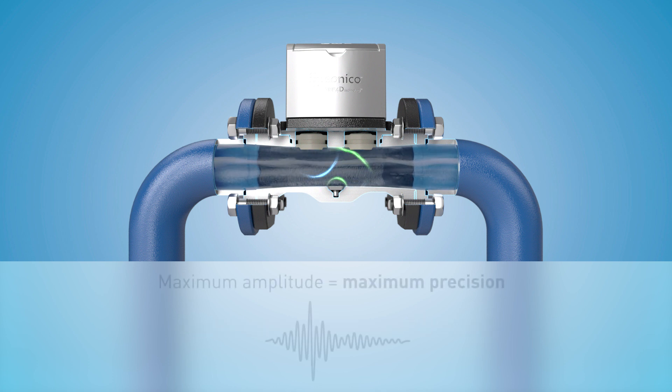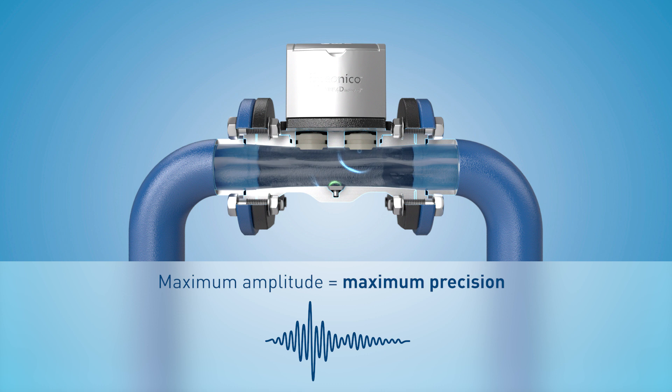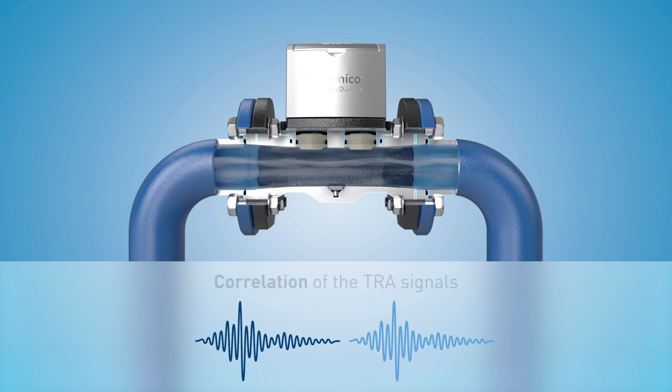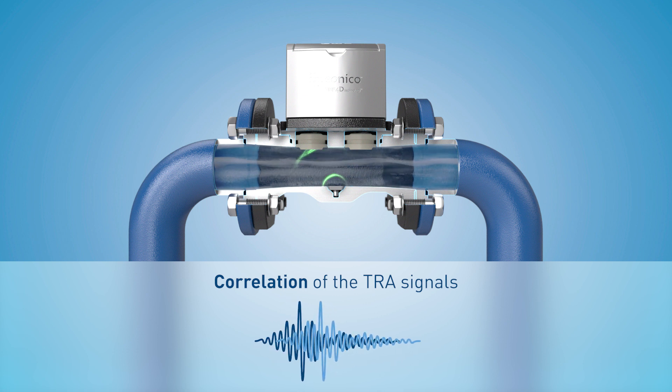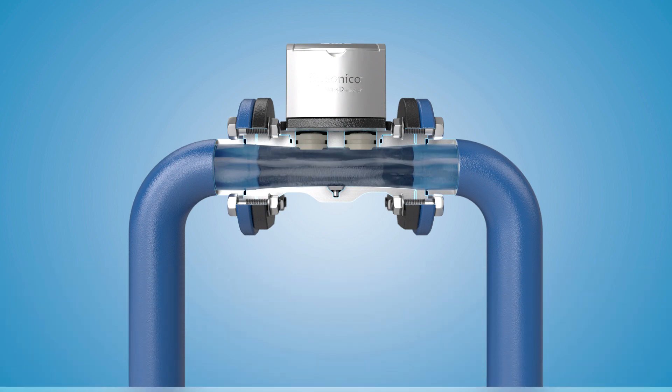The TRA reference signal gives each meter its own DNA, which takes the material and assembly tolerances into account. The reference signal is sent and received following commissioning in the flow and reverse flow direction. The unique shape of the signal means that the amplitude of both directions can be detected with extreme precision. The two signals are now overlapping, enabling the time shift of the two maximum amplitudes to be determined and the flow velocity and flow rate to be calculated.